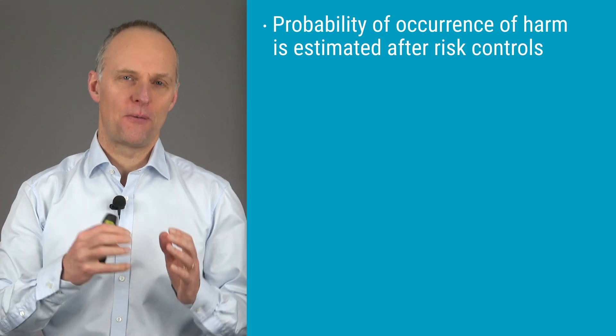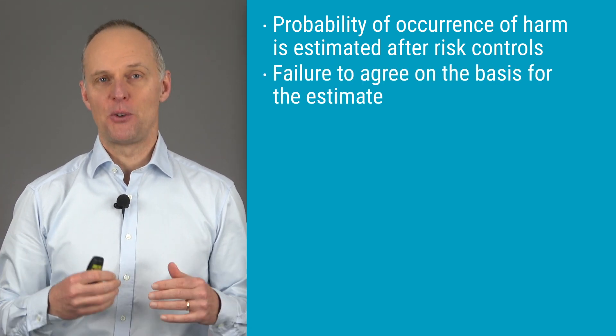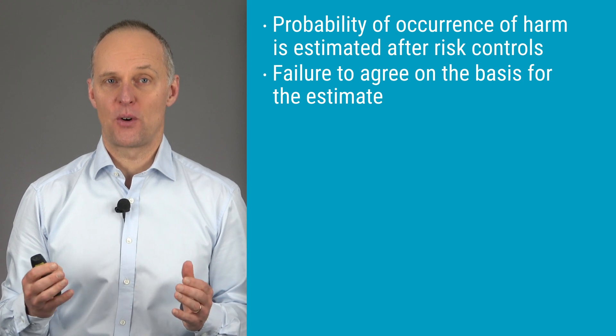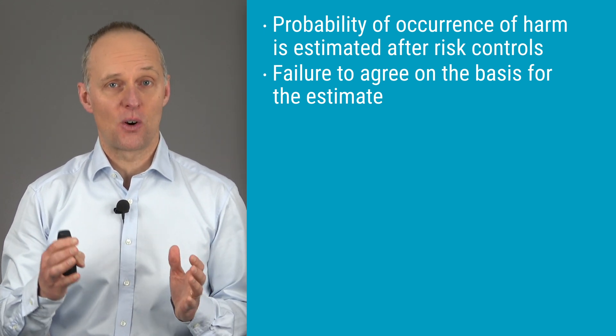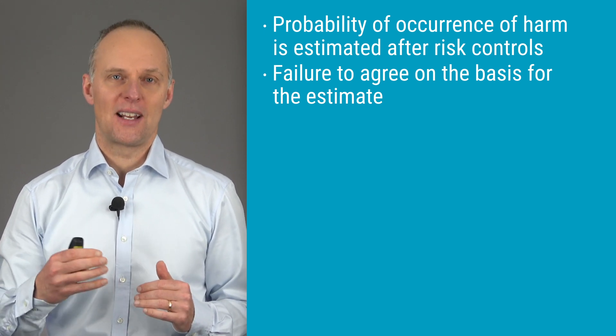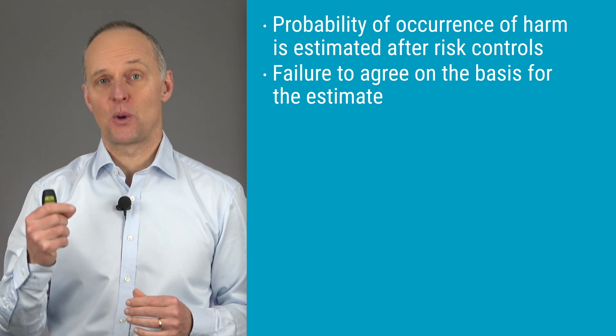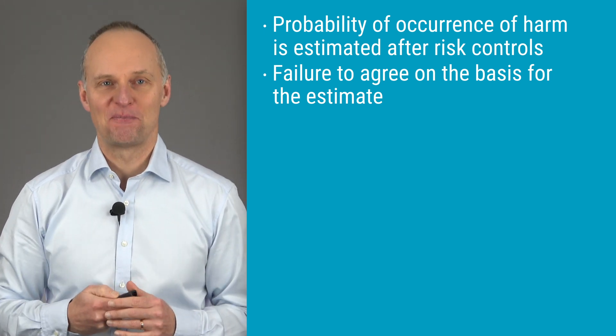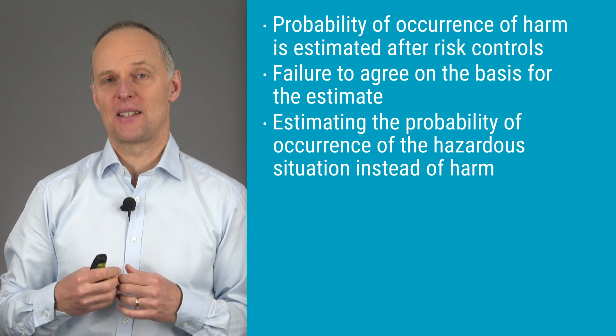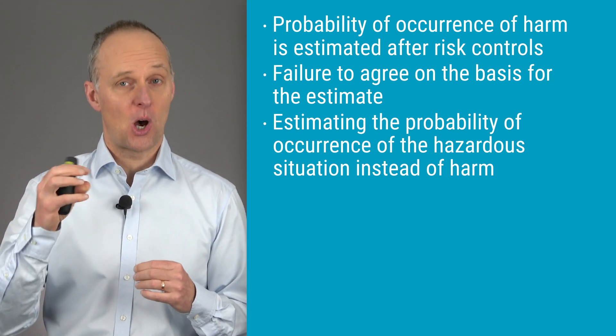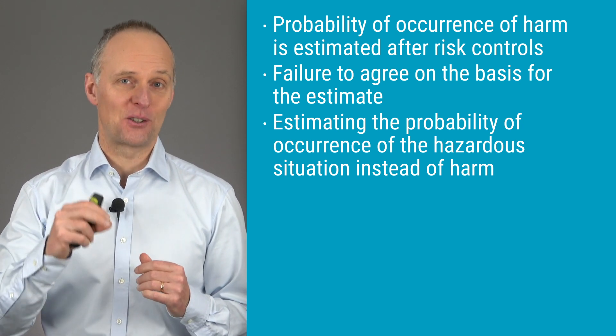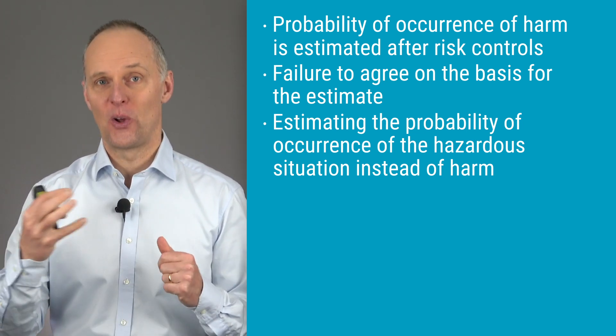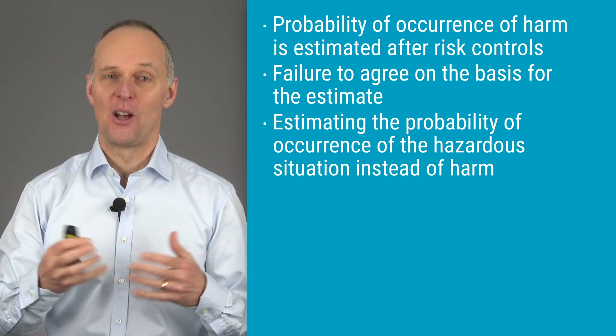Secondly, people don't agree on the basis for the probability of occurrence of harm — one person may think it refers to the probability that harm occurs during one day, a week, or a year, while another thinks it's per use of the device. Team members have to agree on the basis of the probability estimates, otherwise they might argue even though they actually agree. Thirdly, it's quite common that people try to estimate the probability of the hazardous situation instead of the harm. The probability of occurrence of the hazardous situation should normally be referred to as P1, and P1 multiplied by P2 gives the probability of occurrence of harm, or P0.